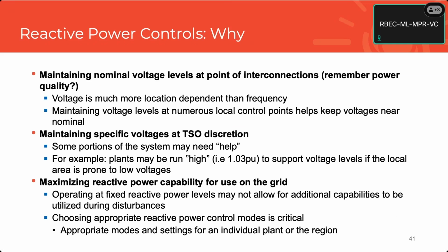So take a quick breath and jump right into reactive power controls. We'll probably skip a lot of the droop discussions. We just did it. But why do you have them? Maintaining voltage levels at points of interconnection is significantly more location dependent than frequency, obviously.